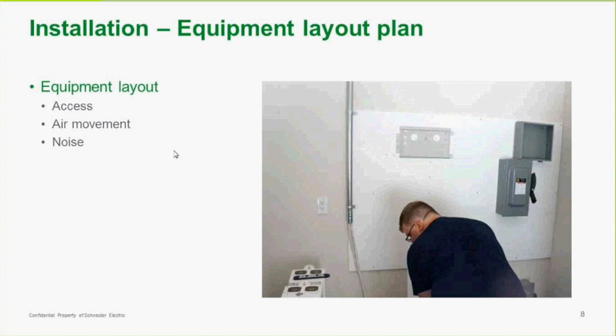There should be an equipment layout plan, and that plan should provide access, some air movement around the equipment. There are fans in the XW Plus, so if we can keep the equipment away from living spaces, it'll keep that living space a little bit quieter. You'll see in this picture there's a back panel that's already installed on the wall. The XW Plus actually hangs on that. So this panel gets installed first, and then the XW gets basically hung right on there.